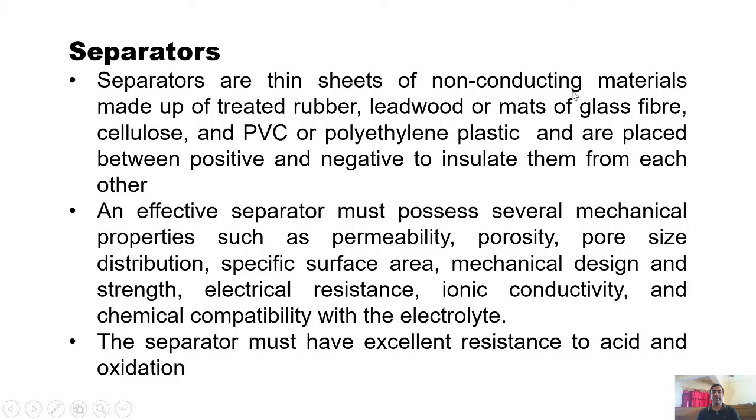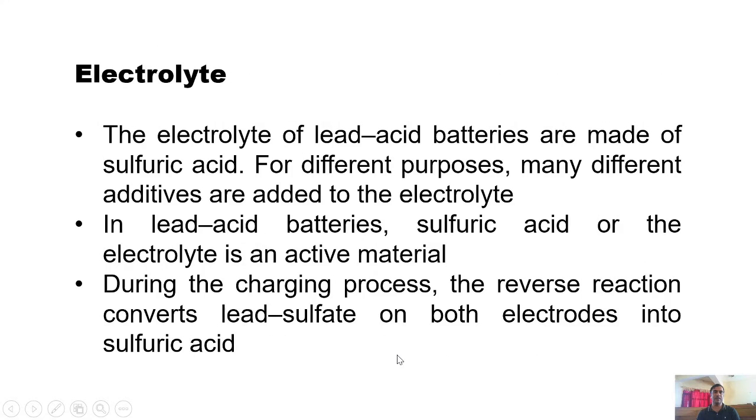Separators are thin sheets of non-conducting materials made up of treated rubber, cellulose, PVC or polyethylene plastic, and are placed between positive and negative electrodes to insulate them from each other. For an effective separator, it must possess several properties such as permeability, porosity, specific surface area, mechanical design, electrical resistance, ionic conductivity, and chemical compatibility with the electrolyte. The separator must have excellent resistance to acid and oxidation.